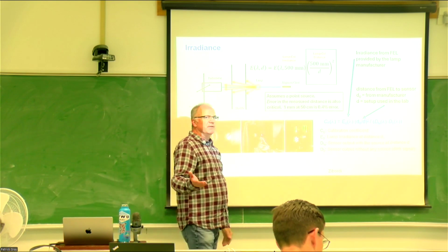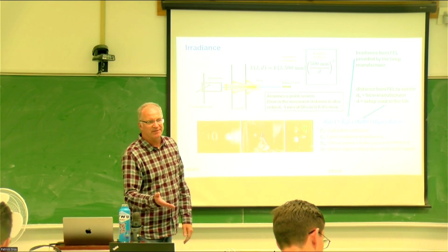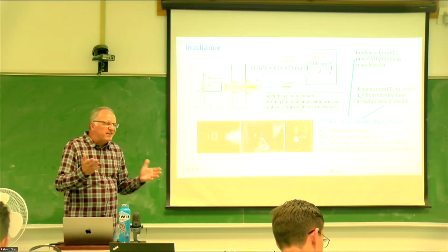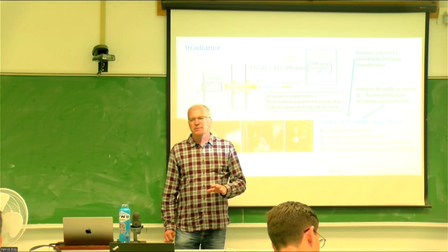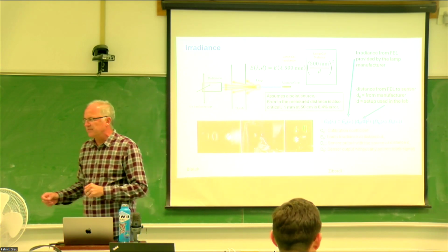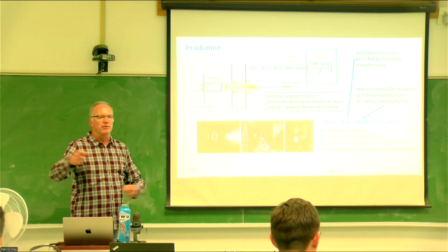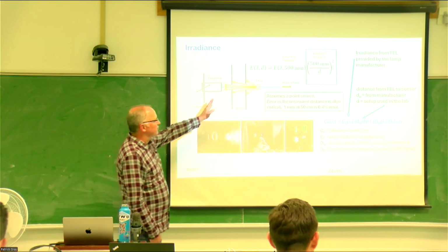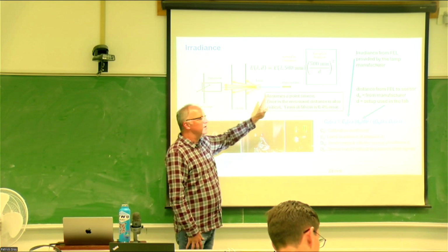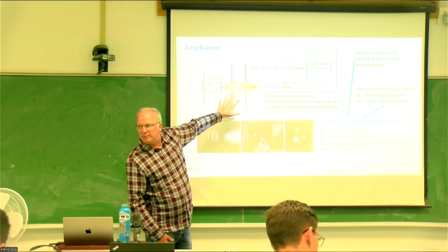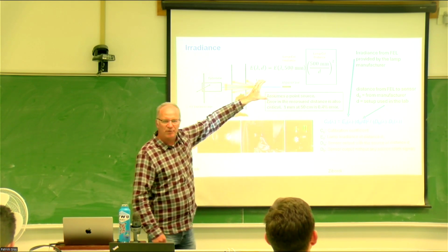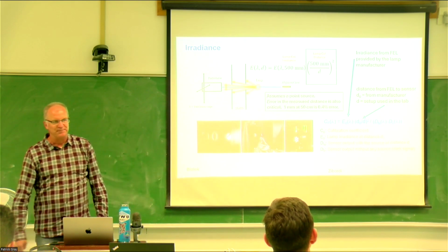Well, because even in that zero photon atmosphere, you've got other stuff in the room. What you're trying to do is not measure what's called stray light in that room, the light that's bouncing off walls, people, all that kind of stuff. And that's why this room is set up so that nobody's allowed over here while we're doing a measurement. People are allowed over here, and then there's going to be another place where people sit behind a curtain as well. So it's a complicated process.